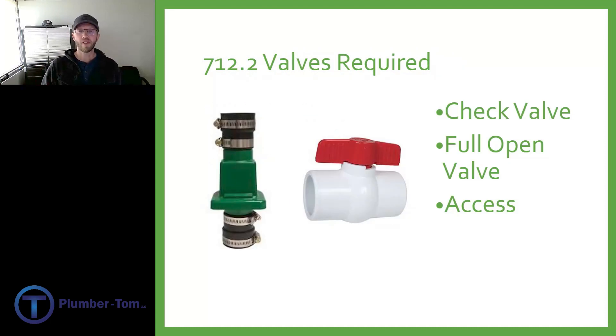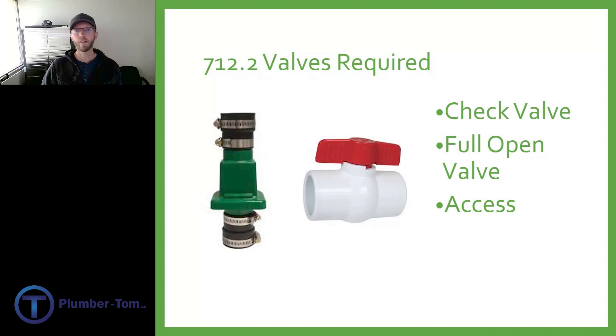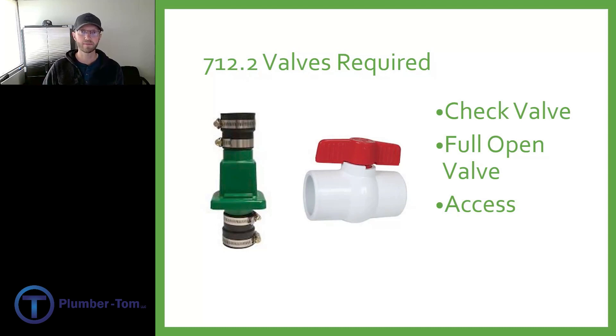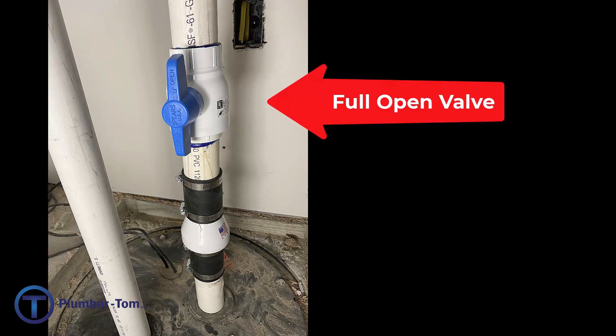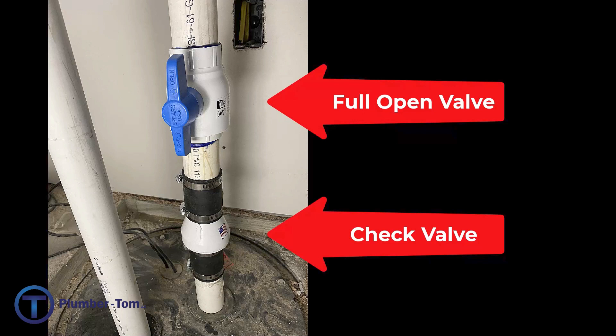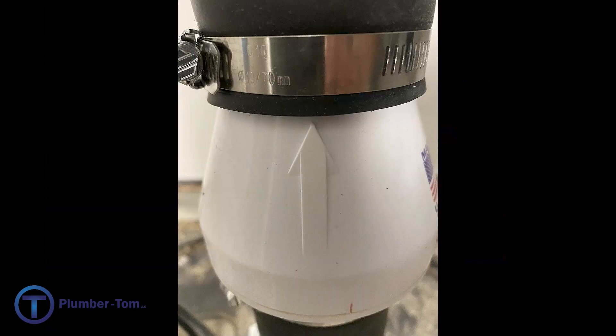712.2 says that valves are required. You would need a check valve to keep fluids from coming back into the sump after they've been pushed up, and a full-open valve so you can close it off for service. Access must also be provided. The full-open valve should go above the check valve so that when you need to service the check valve you can shut off the full-open valve and prevent sewage from flowing out when you take apart the check valve. Also remember that the check valve is directional — there will be an arrow and it must be installed in the correct orientation.